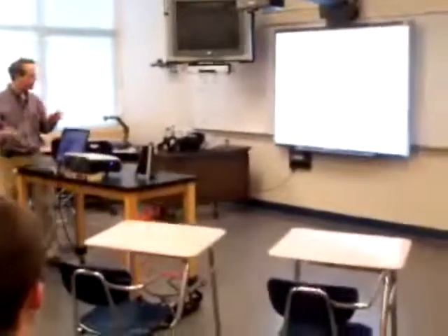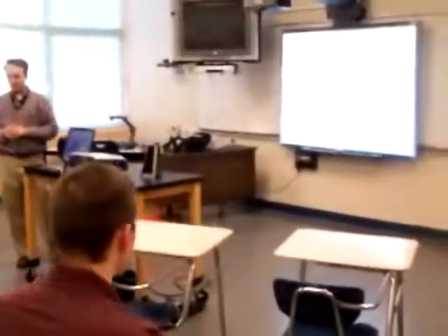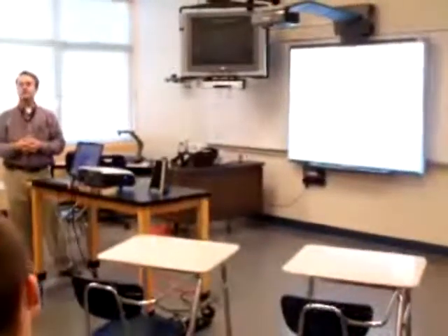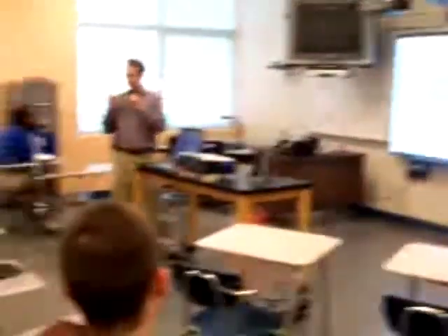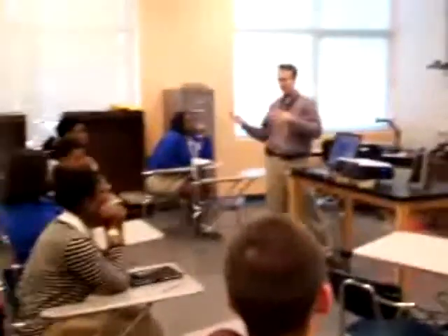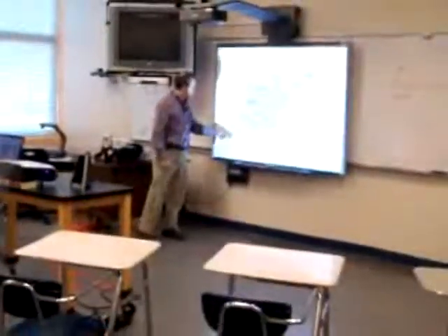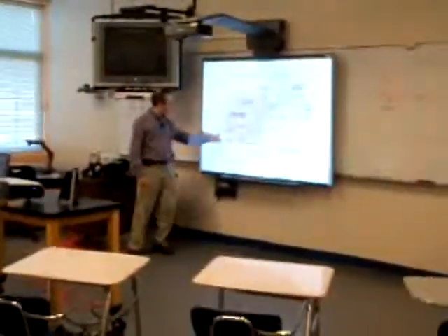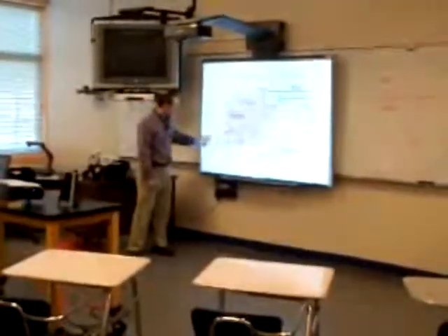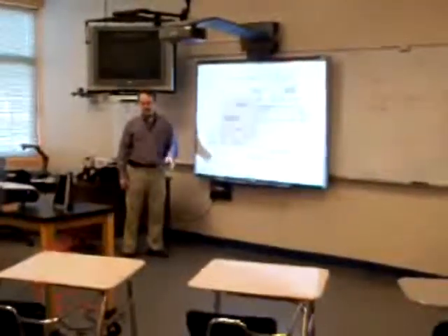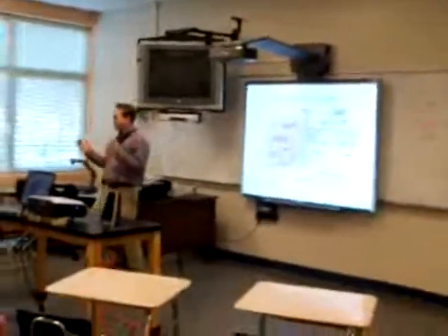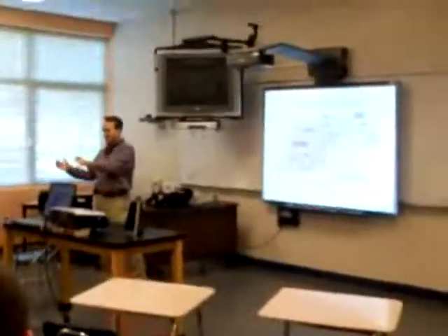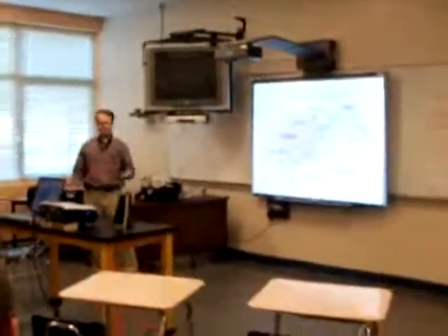All right, geothermal. Geothermal is another way to do heating and cooling. A lot of people think that you drill these wells and you suck the cold water out of the ground, or you suck the hot water out of the ground, and that's what heats and cools. That's not what it is. All these wells down here, and they're 300 feet deep, by the way. The pipe goes down and it does a U-turn and it comes back. And the whole system of wells replaces what the condensing unit does at your house, okay? It's just a place to dump the heat.